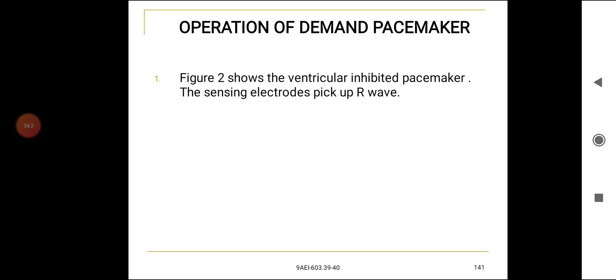Operation of demand pacemaker. The figure shows the ventricular inhibited pacemaker. The sensing electrodes pick up the R wave. The refractory circuit provides a period of time following an output pulse or sensed R wave, during which the amplifier in the sensing circuit will not respond to outside signals. The sensing circuit detects the R wave and resets the oscillator. The reversion circuit allows the amplifier to detect R wave at a low signal to noise ratio. In the absence of R wave, it allows the oscillator in the timing circuit to deliver pulses at its preset rate.